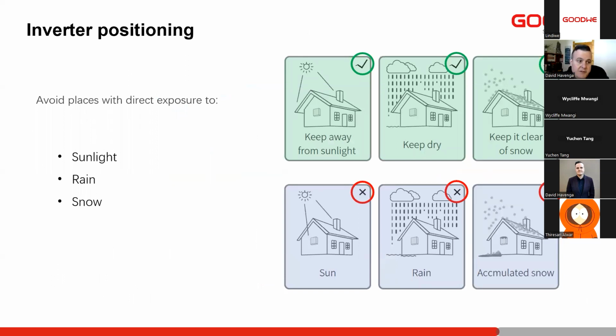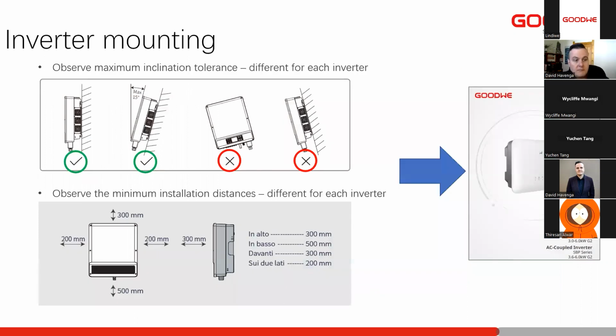The inverter positioning, all of this you can find also in the user manuals, and you can just double check in the user manuals before installing. So our hybrid inverters are IP65 rated. They can be installed outdoors, but we need to make sure that they are not in direct sunlight, not in direct weather conditions, and do not have direct snowfall on them. The inverters can be installed at a backwards incline. We should not install them sideways or leaning forwards. This is all about heat dissipation.